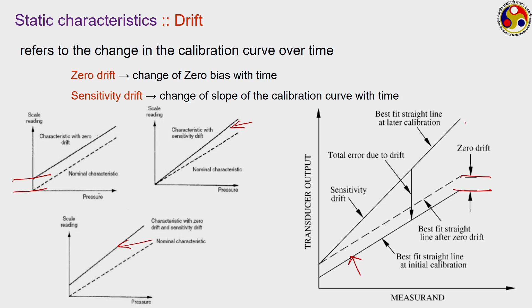When that kind of situation arises, we may have to go for recalibration. This was the original curve, but now we can see a zero drift has developed, along with a sensitivity drift. So if you recalibrate, this new curve may emerge as the new calibration curve. This drift therefore necessitates repeated or periodic calibration of your instrument.